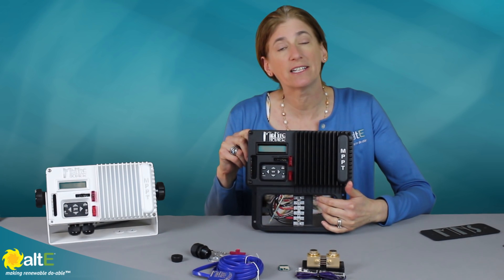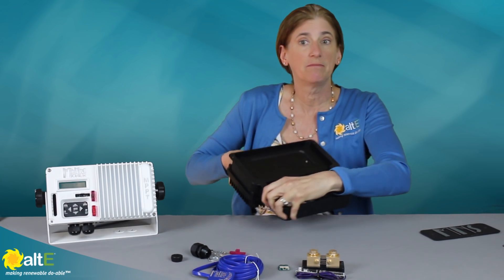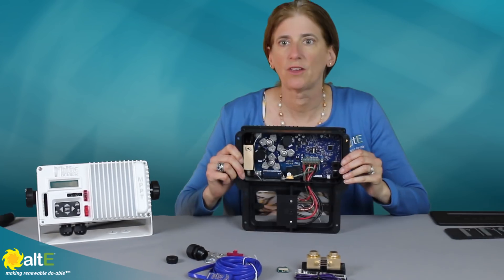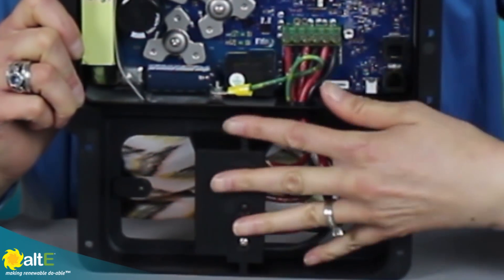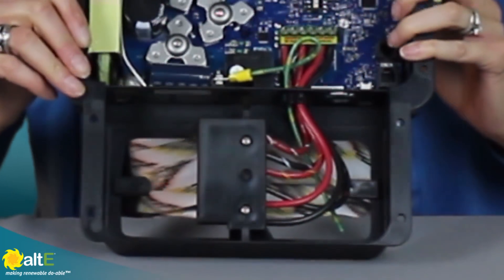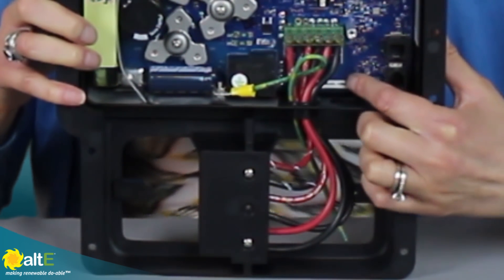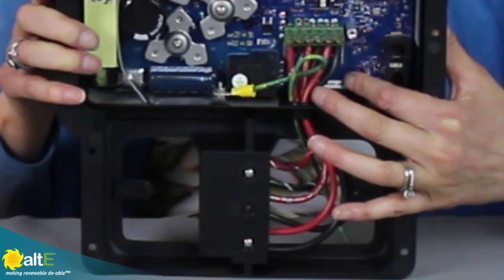If you do want to use some of the advanced features, let me show you inside the back of the charge controller. It's simply one screw — we take that off and get in there. You can see where this wiring harness connects up to the existing one. So again, if you don't have the space for the flush mount, you can just unscrew those and connect your wires right there. Next to the wiring harness, we've got a micro USB port. This is to upload any firmware updates — you just plug in a micro USB drive and upload any newer firmware released by Midnite.